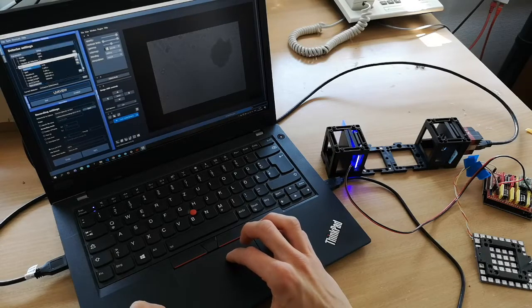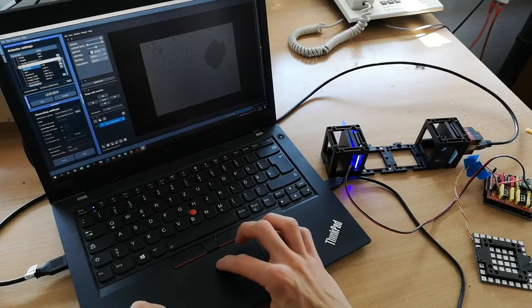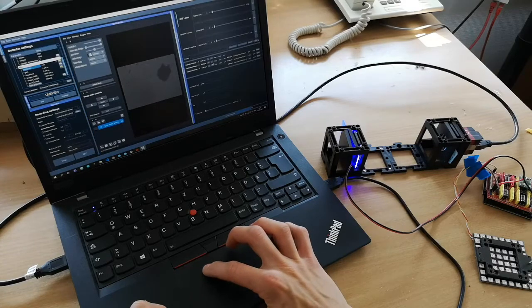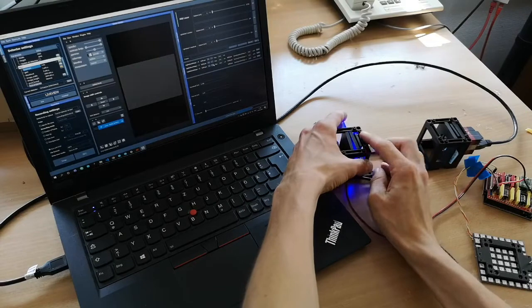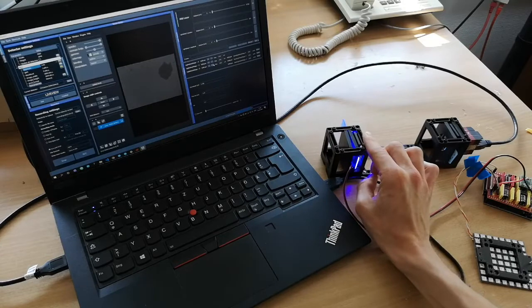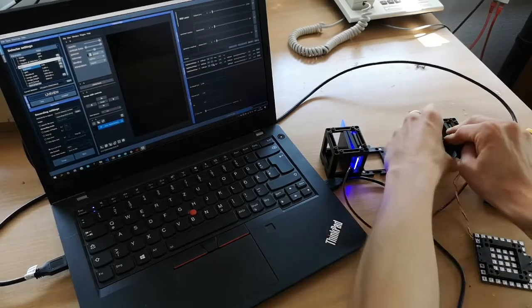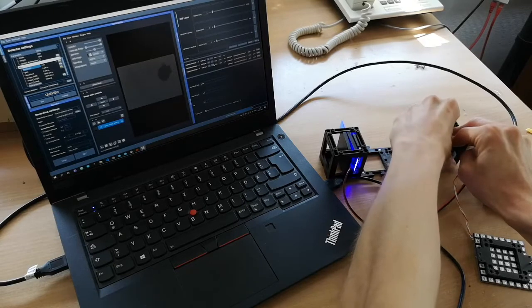What we're going to do now is try to reconstruct it, or better, refocus that. So we minimize these pictures here so that we see it a little bit better. If you don't see this kind of image, play with the position of the pinhole. I just move it a tiny bit. The pinhole has to be very centered with respect to the LED intensity peak in the center, and then also find the spots of the sample that are somewhat interesting, like the leaf here.